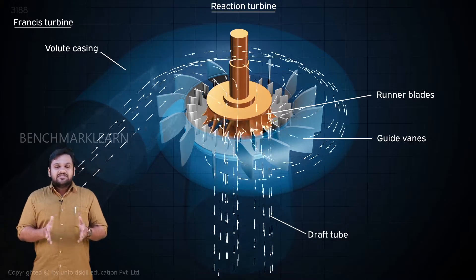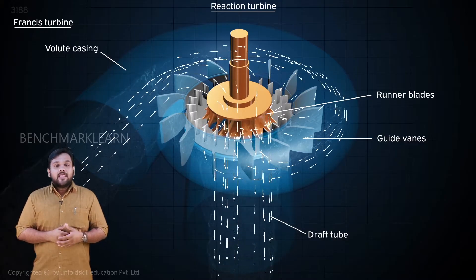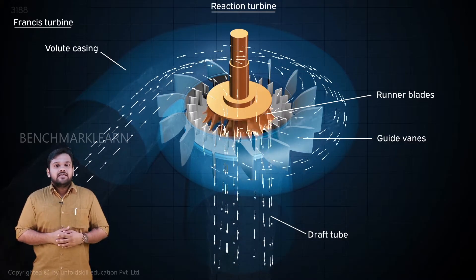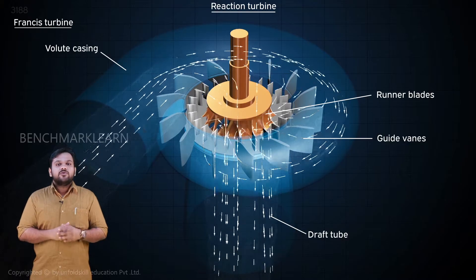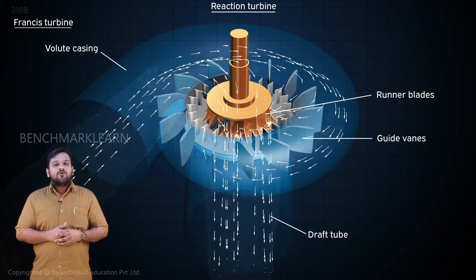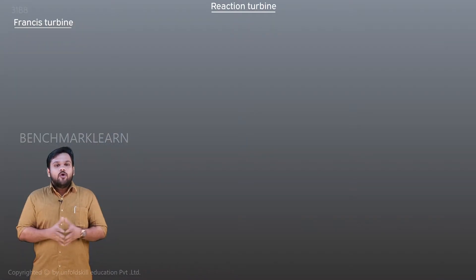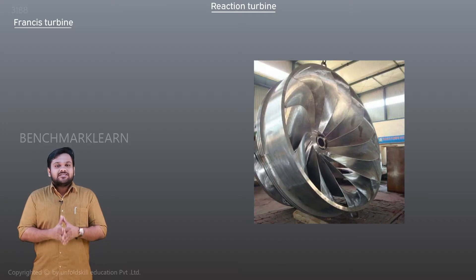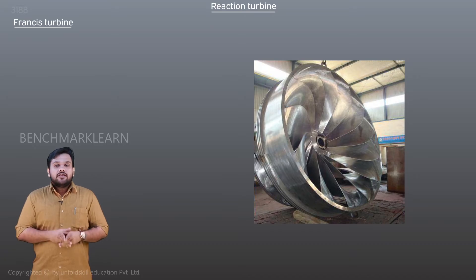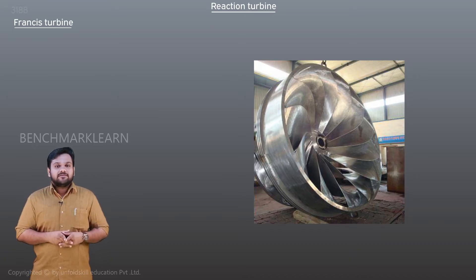Since the water enters radially and leaves the turbine axially, the Francis turbine is also known as a mixed flow turbine. The Lower Periyar project in Kerala uses three Francis turbines of 20 megawatt each at a rated head of 184 meters.